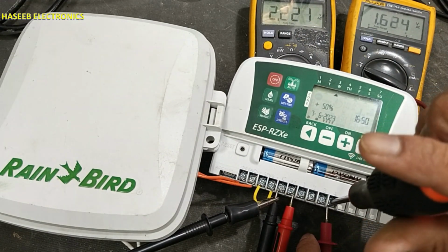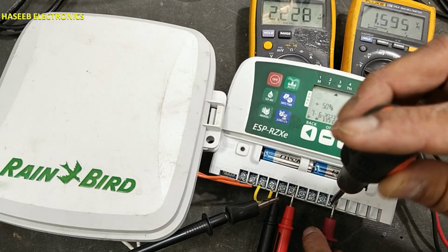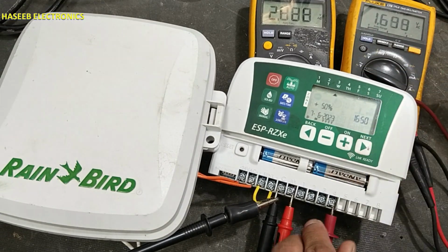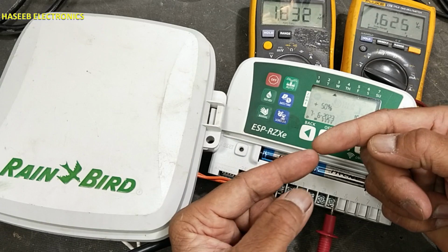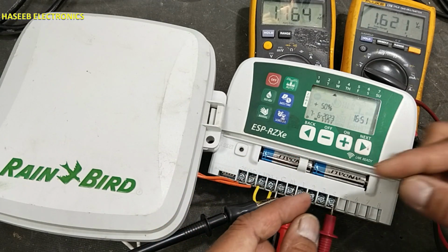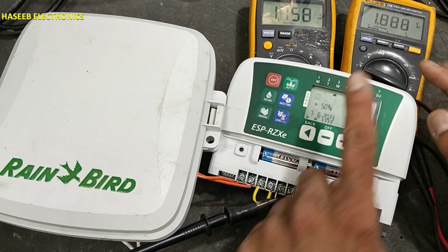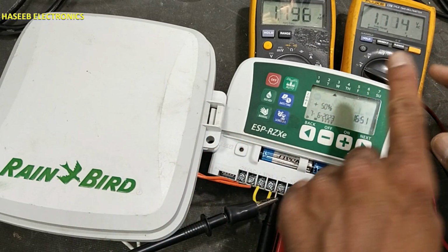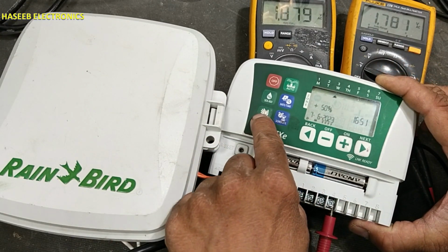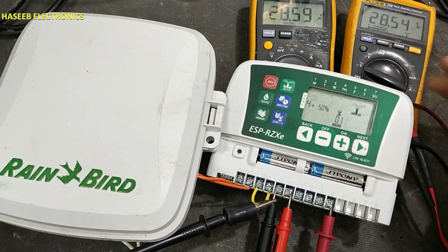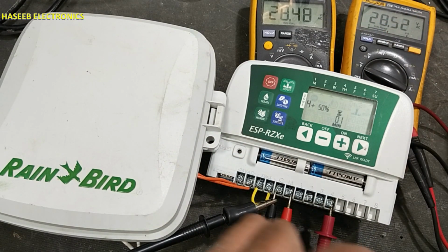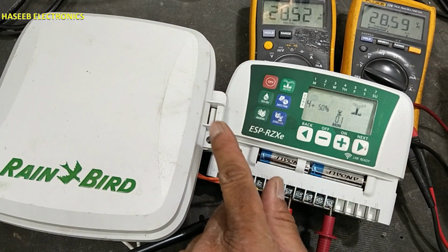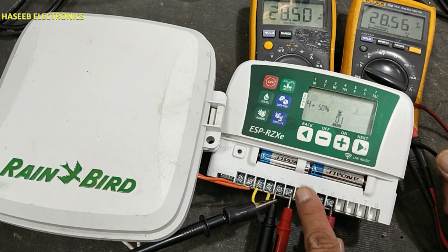Now we will test number 4. Before this, these channels were providing 15 volt, 16 volt due to disconnection and some loose circuit. But after replacing that track, now the voltage is good. Auto. Yes, excellent. All 4 channels are now turning on with master valve.